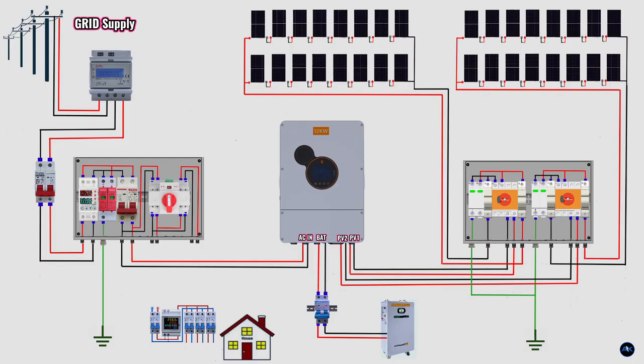From the surge protector, the cables go into an AC circuit breaker rated for the inverter output. This breaker protects the inverter from overloads and short circuits. Now the inverter's AC output is connected to the load distribution board. Each group of loads, such as lights or sockets, is protected by its own load circuit breaker. If the system includes grid and backup power sources, an automatic transfer switch, or ATS, is installed. The ATS safely switches the power source between grid, inverter, or generator without any backfeeding.